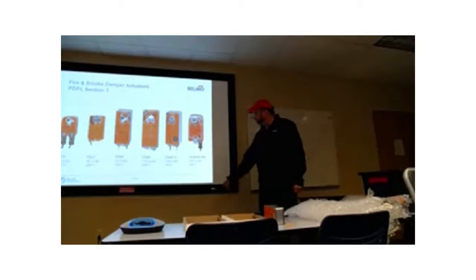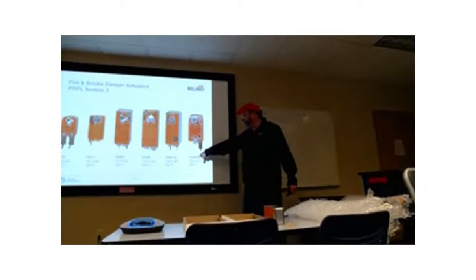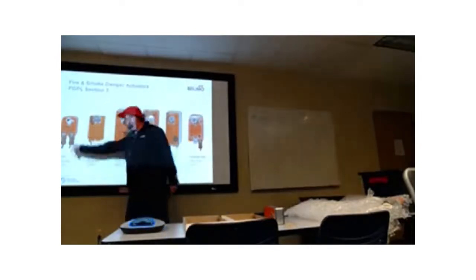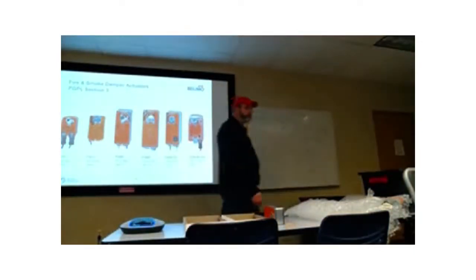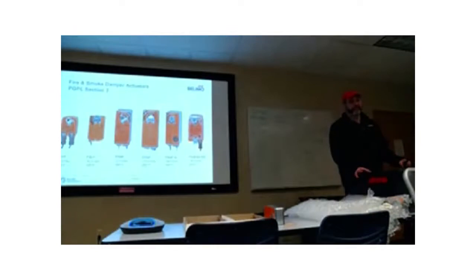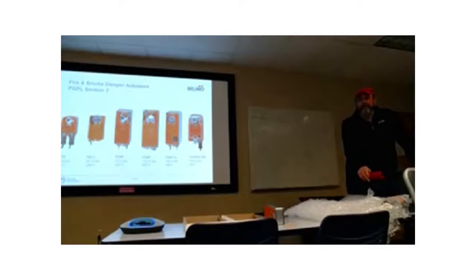But notice here we go all the way up to 180 inch-pounds on the big guy, the FSAF, and down to the little guys here, the FSTF. Now I want to say something about these fire smoke damper actuators. These are specifically for life safety stuff. They're only made for the fire smoke damper assemblies you guys have in the buildings.